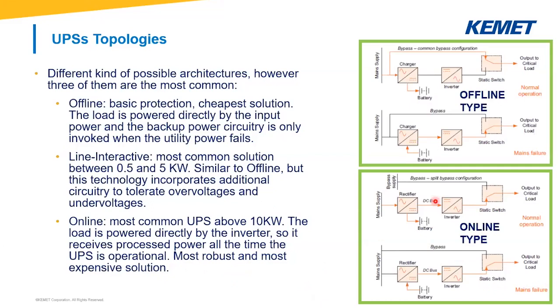As you can see in the image on the right, during normal operation — differently from what happens in the offline type — the switch is down, so power comes from the inverter even during normal operation. During a mains failure, the switch stays down the same, and even in this case power comes from the inverter. I will focus in the next slides on this kind of architecture because it's the most interesting one for designers, and I will show you in more detail the different operational modes we can have.